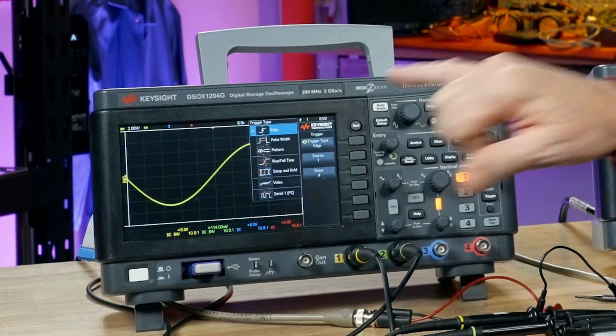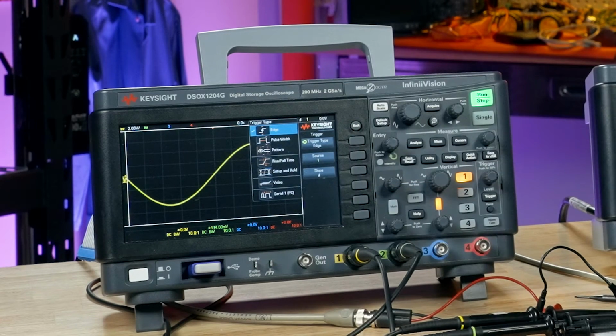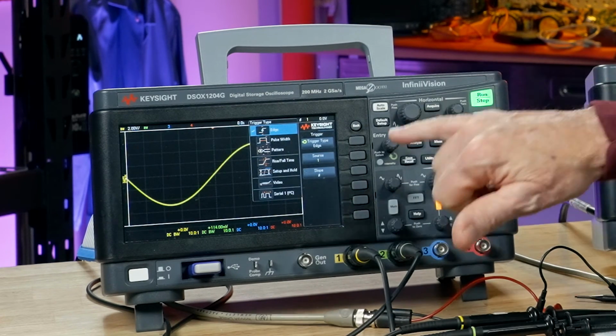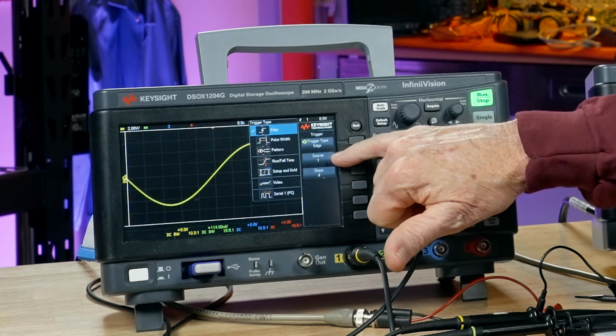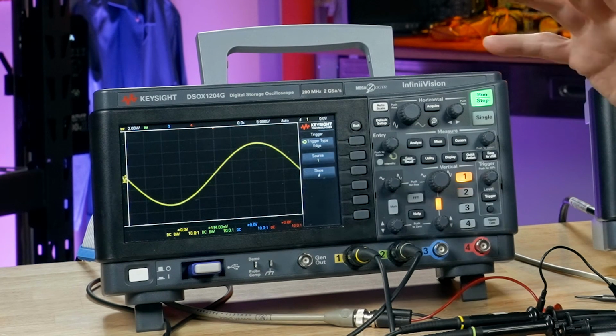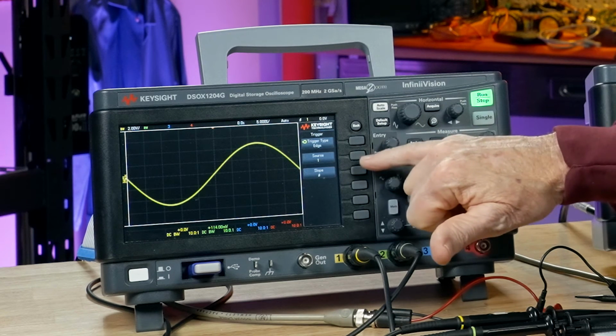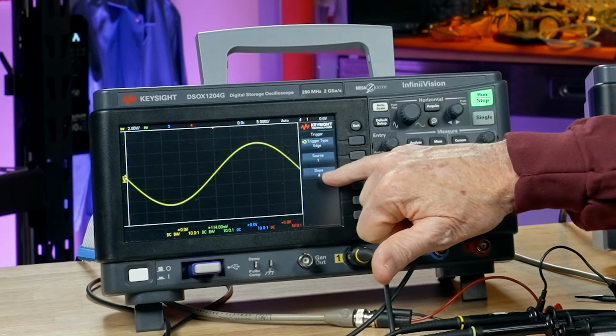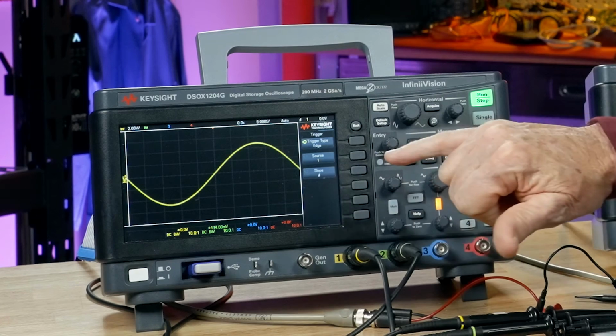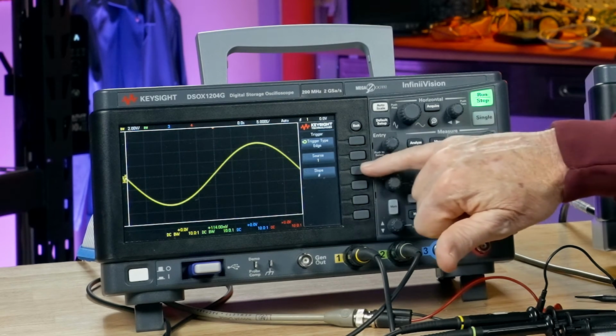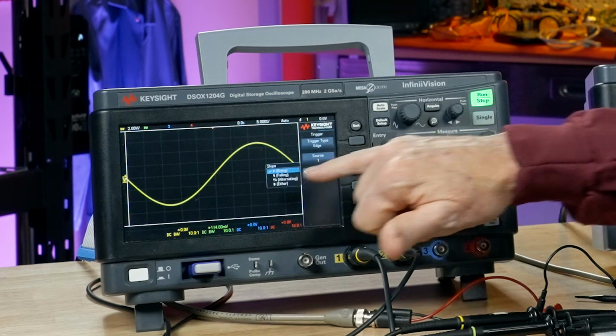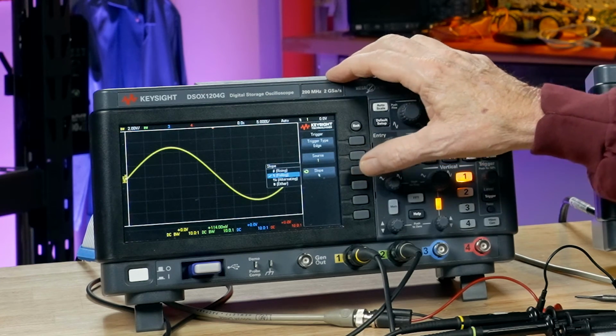These are some advanced trigger types that we're going to see in one of the later lessons. But we're triggering on an edge of the signal, and that's what you'll be using most of the time. It also says we're triggering on channel 1. We could change that to channel 2, but channel 1 is our trigger source. And it says we're triggering on a rising edge. Now, we can trigger on a falling edge if we like. If I press slope, I could change it to falling.